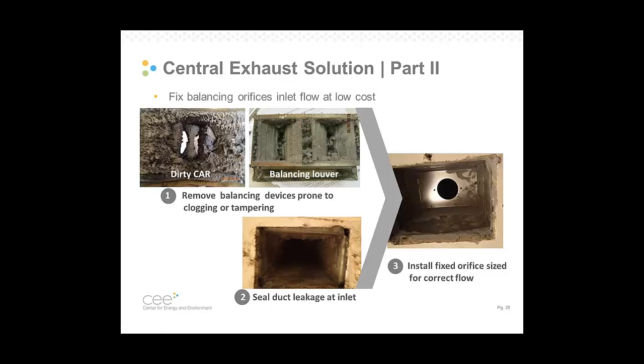Balancing louvers here also have the potential to clog up, but another issue with them is that occupants may adjust or alter them. They're right behind the register, and occupants may open them or fully shut them, and that affects flow not only to their unit but to the whole shaft or duct that multiple apartment units are on.